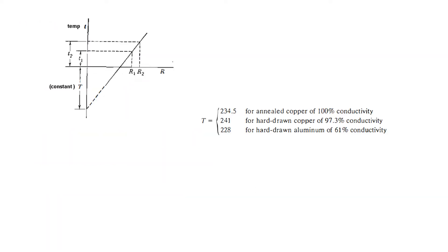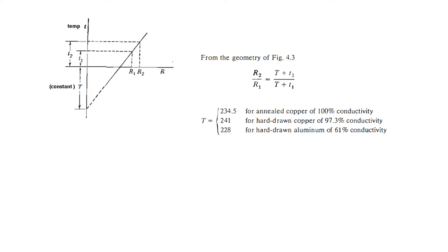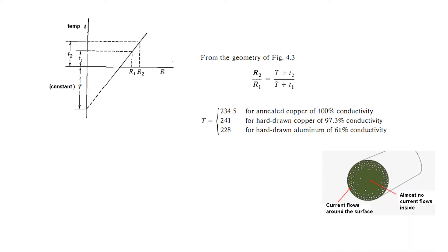Resistance is also dependent on temperature. We use a formula to calculate resistance at two temperatures. The first temperature is T1 with resistance R1, and the second temperature is T2 with resistance R2, linearly defined by this equation. For hard-drawn aluminum, the constant T is 228.